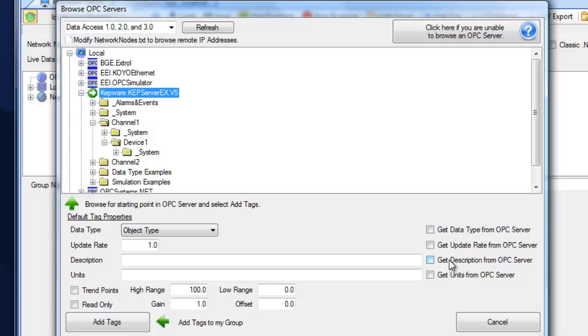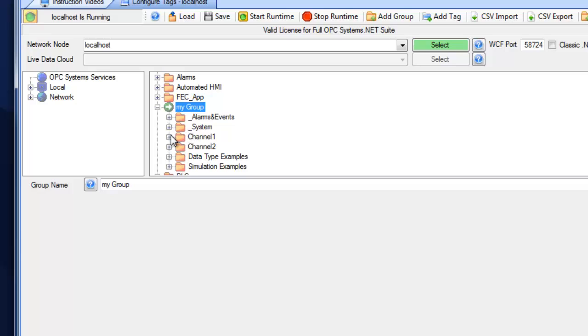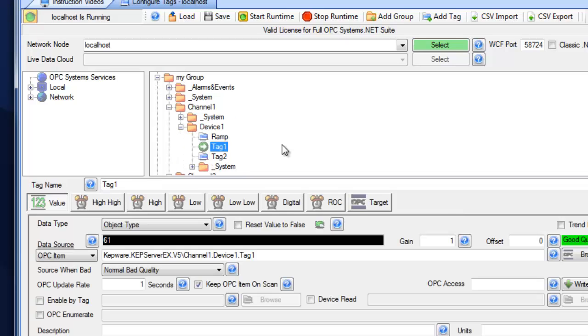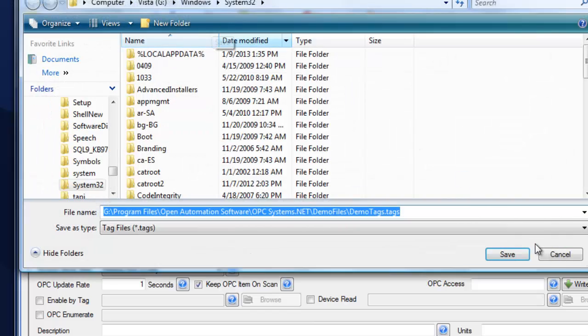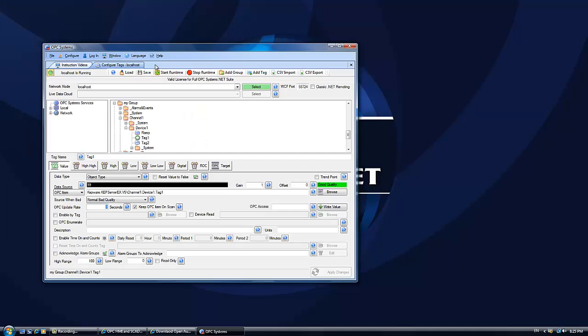Optionally, you can also retrieve the data type, description, and other attributes from the OPC server while adding tags. When you select Add Tags, it goes to the OPC server, obtains all OPC items, and automatically adds them into the real-time service. There are other ways to connect to OPC servers directly from client applications using Direct OPC — we have a separate short video on that at opcsystems.com. Because the service is in runtime, it will begin communicating with the OPC server, and any value changes at the specified update rate will come in. You would then save the tag configuration with the Save button, and under Configure Options specify the file to automatically load tags when the service restarts.